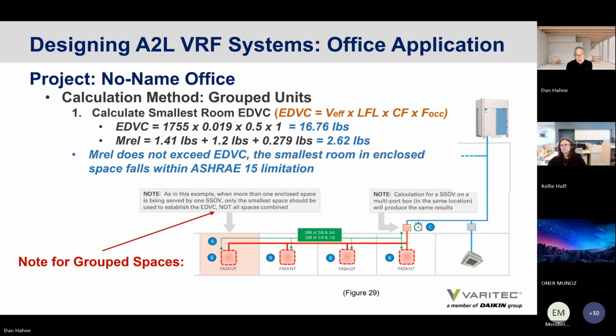Good to know. Yep. So my question is, usually we don't take an ASHRAE standard as a code requirement until it's adopted by certain years of mechanical code. Do you have any exposure to a jurisdiction telling you that you have to go with the original ASHRAE Standard 15 2022 version? Because all those addendums are to the 15-2024 version. So whether that's applicable or not, have you heard anything? Being very literal to the law, we have to comply with the 22 version of ASHRAE 15. But the 2022 version of 15 is not written out very, let's say, perfectly, so we have to reference a lot of the 24 version of the standard. Have you heard anything in that regard?